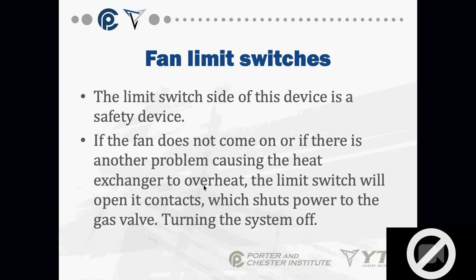The limit side of this device is a safety device. If the fan does not come on, or if there's another problem causing the heat exchanger to overheat, the limit switch will open its contacts and shut power down to, well, this says gas valve, but it's the oil burner. Shuts my ignition off. Okay? Shuts off all my flame. We use the same control on gas. That's why it said gas valve there. But the oil burner turns the system off. Okay?